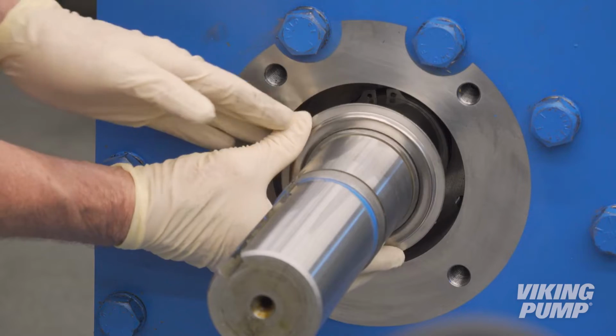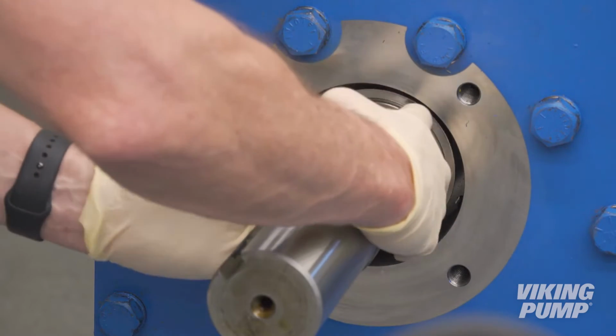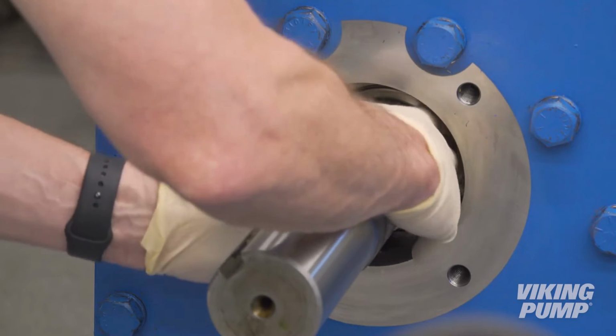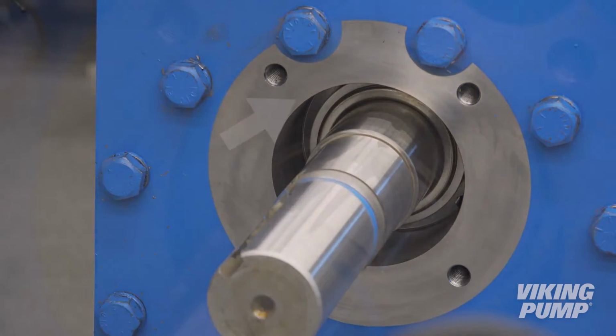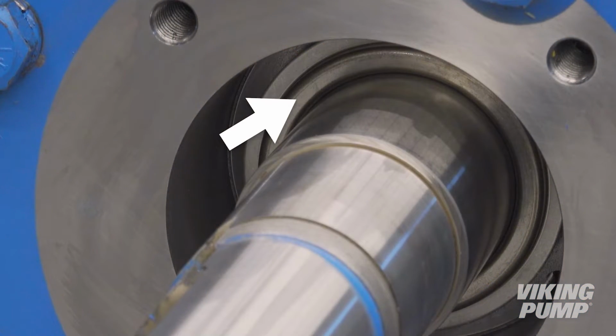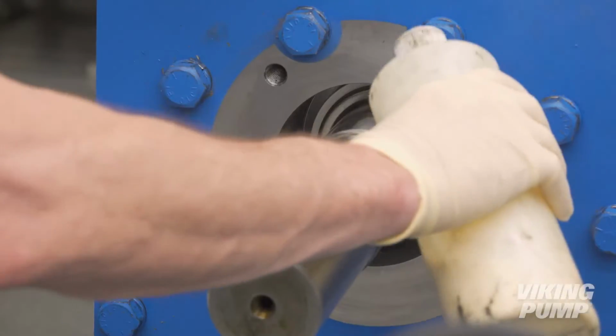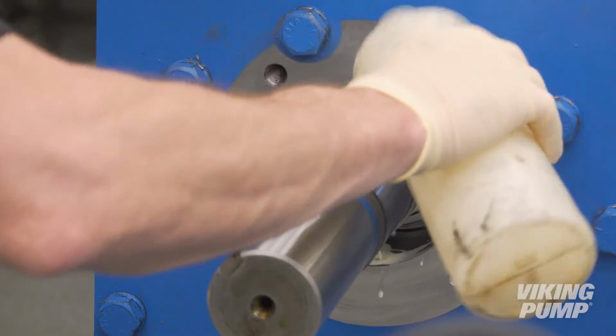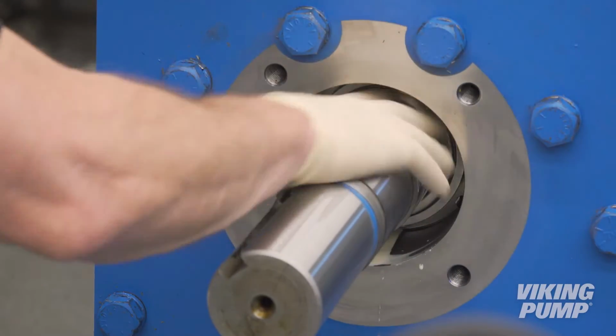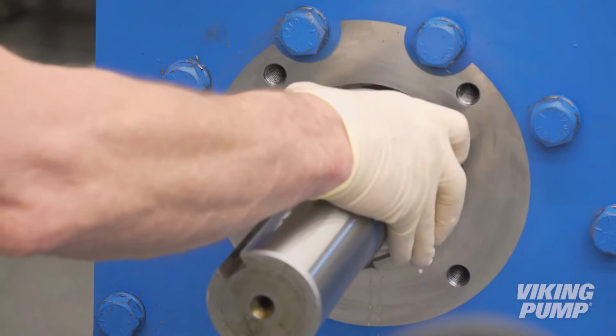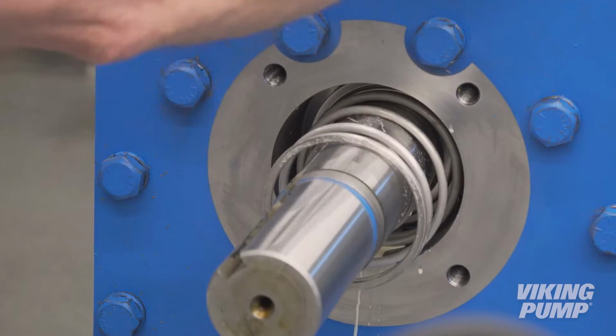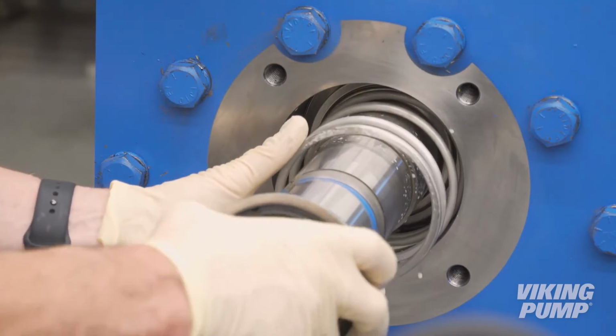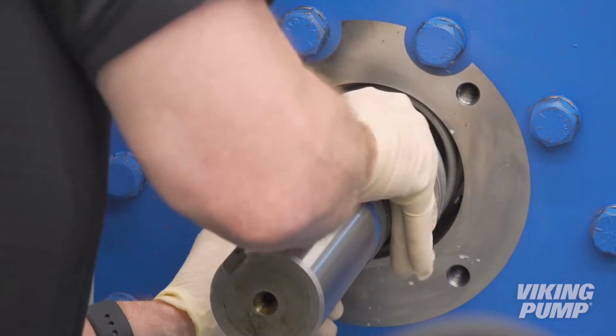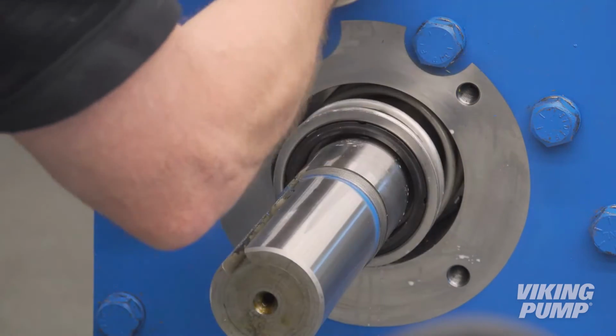Place the spring guide onto the shaft, making sure that it is fully seated against the snap ring, with the cup section of the spring guide facing outward toward the motor end of the shaft. Coat the shaft and the inner diameter of the mechanical seal with P80 lubricant and install. Make sure the seal spring is fully seated with the spring guide. Clean the seal faces with a lint-free cloth and isopropyl alcohol or another suitable cleaner.